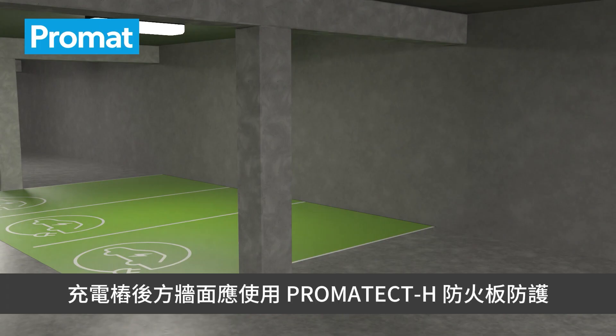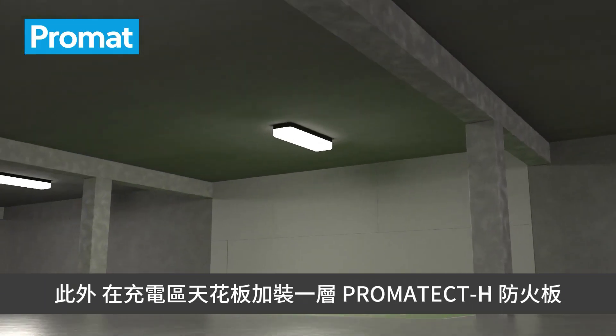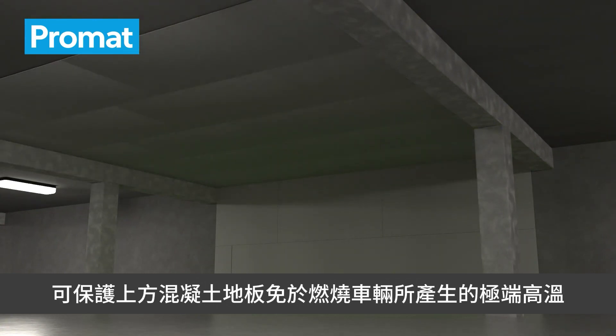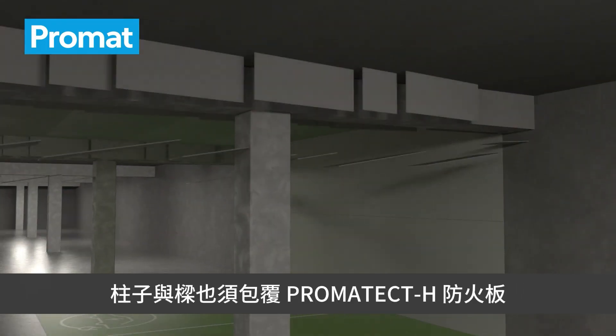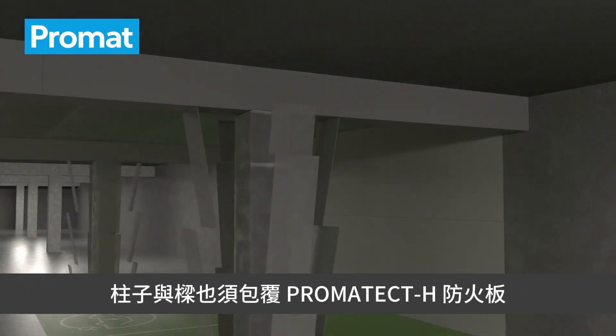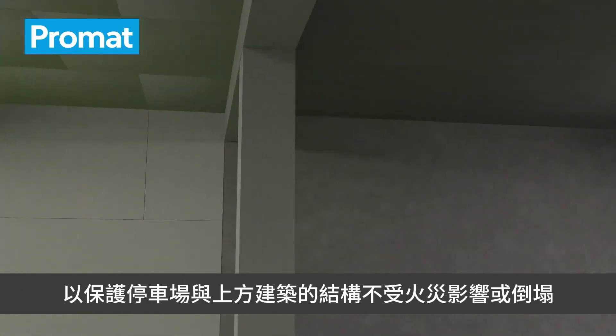The wall behind the charging units needs to be protected with PROMATECT-H boards. Additionally, a layer of PROMATECT-H boards fixed against the ceiling of the charging area will protect the concrete floor above against the extreme heat produced by burning cars, preventing structural damage or even collapse of the concrete slab above the cars. Beams and columns are also covered with PROMATECT-H boards to protect the load-bearing structure of the car park and the building above from damage or collapse.